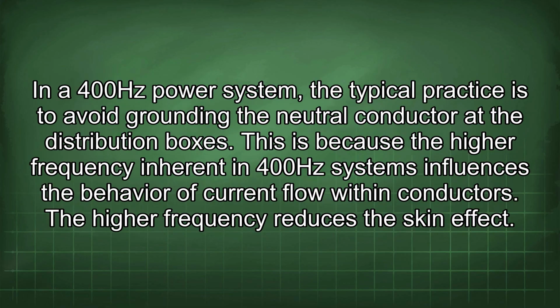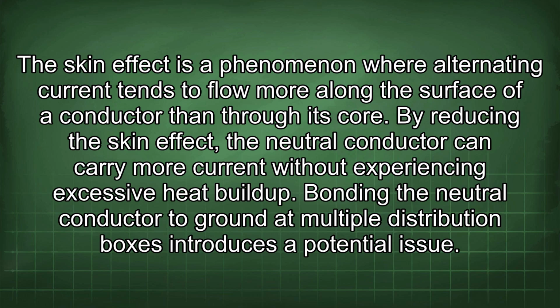In a 400 Hz power system, the typical practice is to avoid grounding the neutral conductor at the distribution boxes. This is because the higher frequency inherent in 400 Hz systems influences the behavior of current flow within conductors. The higher frequency reduces the skin effect. The skin effect is a phenomenon where alternating current tends to flow more along the surface of a conductor than through its core. By reducing the skin effect, the neutral conductor can carry more current without experiencing excessive heat buildup.